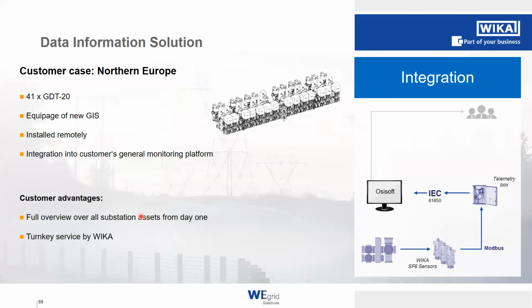Also, we have a customer case that we just finished recently, where we supplied 41 sensors for a completely new GIS, because for this customer, it is now legally specified that they need to monitor their equipment in the transmission grid online. So not only GIS, but also transformers and shunt reactors and other equipment in the substation. And here we had to integrate this solution into the customer's general monitoring platform. They are running a monitoring platform from the American company OSIsoft to control all of their assets.